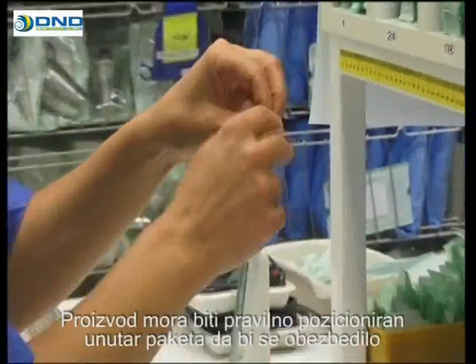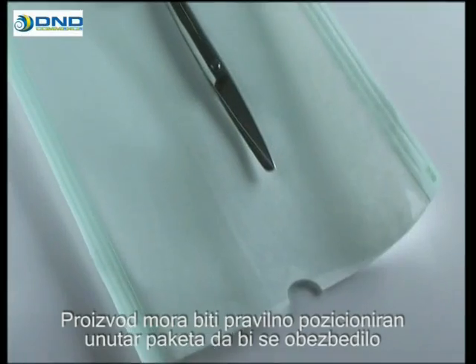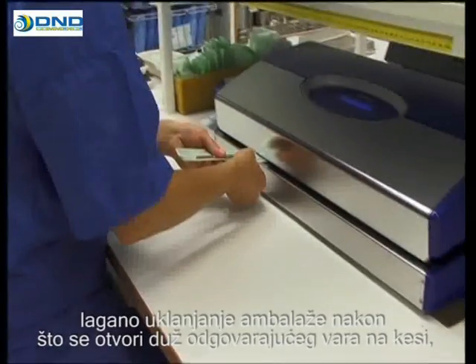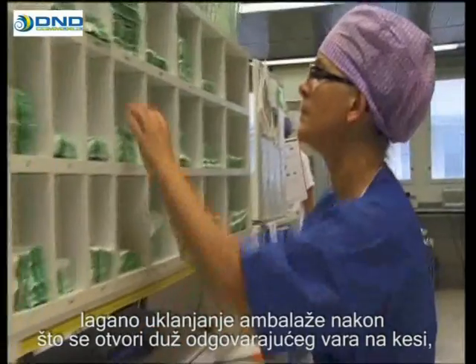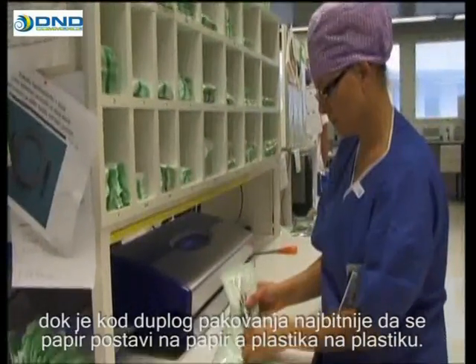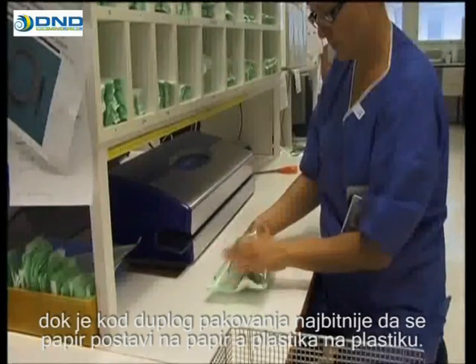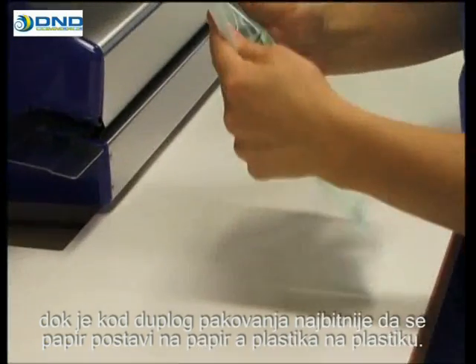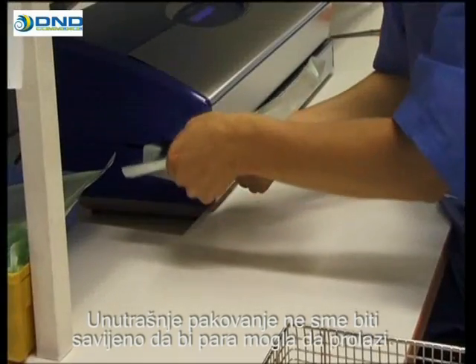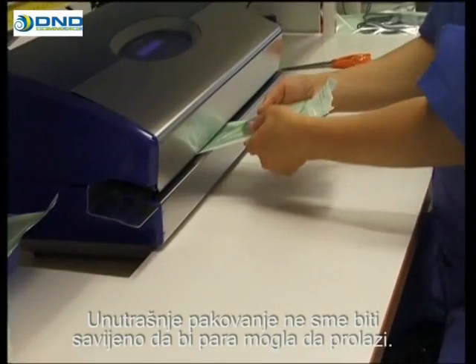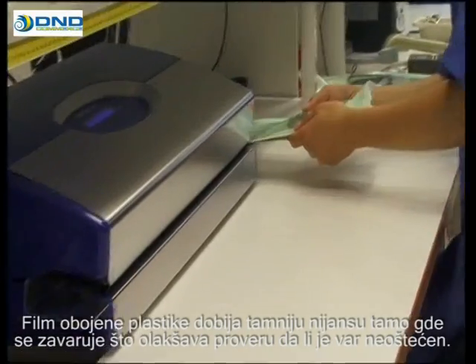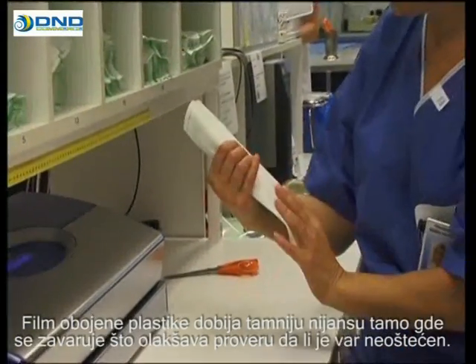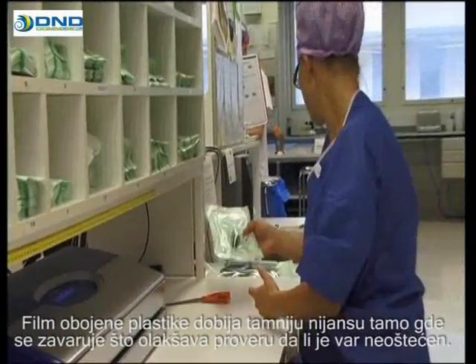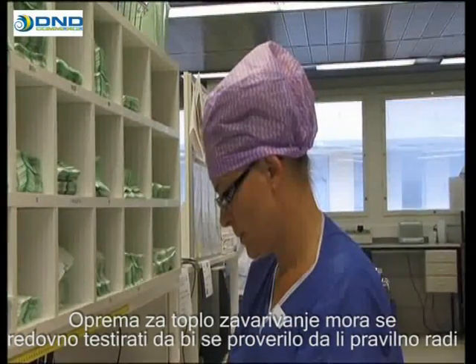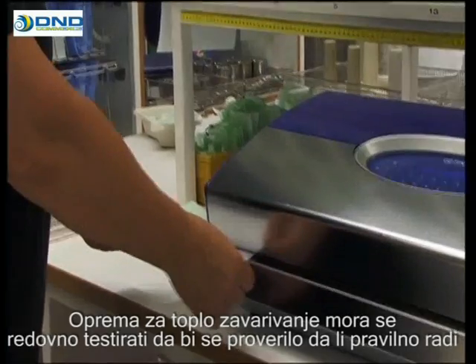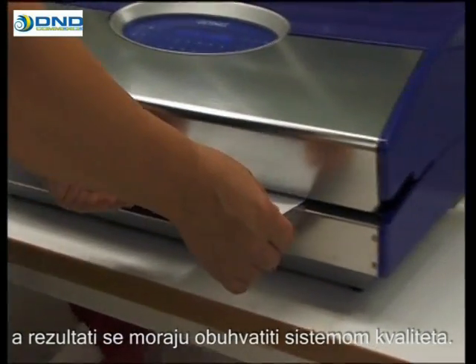The product should be positioned correctly inside the package to enable easy removal of the packaging after it's been opened along the appropriate seal. Where double packaging is required, it's important to position paper against paper and laminate against laminate. The inner packaging must not be folded so that the passage of steam remains unhindered. The colored plastic film turns a darker shade where the sealing has taken place, making it easy to check that the seal is intact. The heat sealing equipment must be tested regularly to validate that it's functioning properly, and the test results must be filed as part of the quality system.